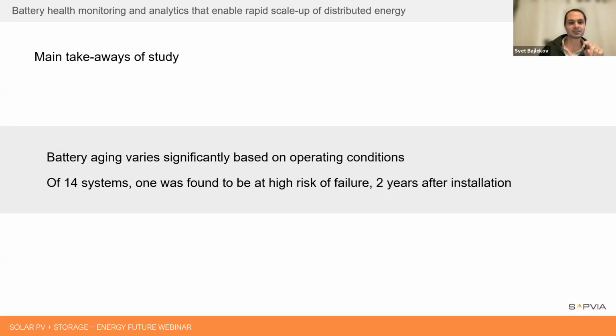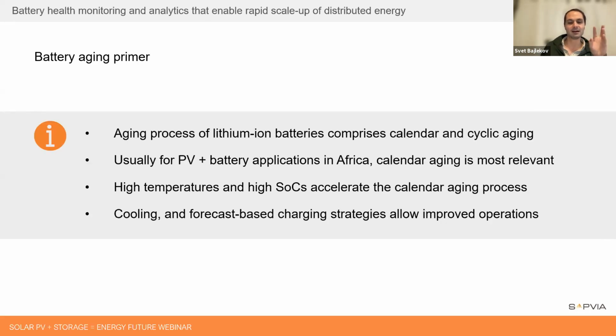Sticking with this for another minute: in terms of calendar aging, high temperature and high states of charge are the main drivers there, they accelerate the aging process. It's a little counterintuitive, especially coming from the lead acid battery world, where a low state of charge causes degradation. Here in lithium-ion, you don't want to have a 100% state of charge battery just sitting around, that's what causes aging. On the counterpoint, if you cool your battery and have a charging strategy based on consumption forecasts, that can improve your operations.